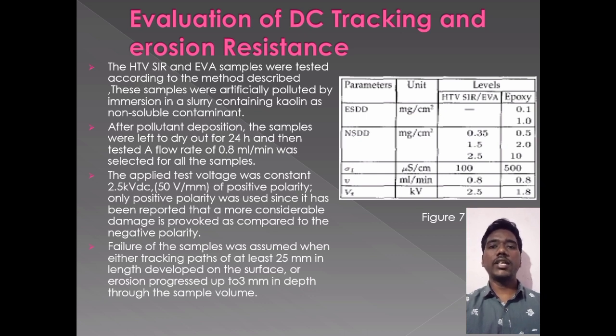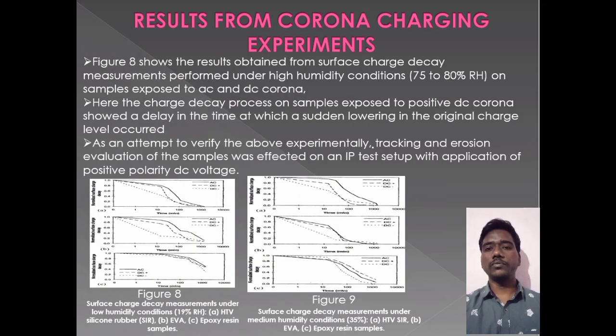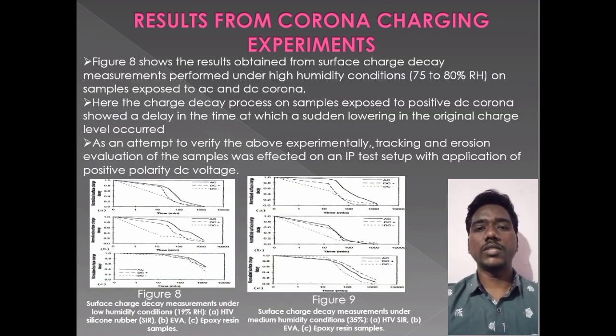The general test conditions employed for both methods are summarized in the figure. Failure of samples was assumed when either tracking paths of at least 25 mm in length developed on the surface or erosion progressed up to 3 mm in depth through the sample volume. Results from corona charging experiments.